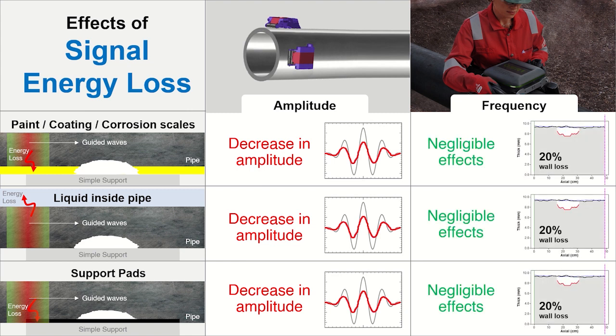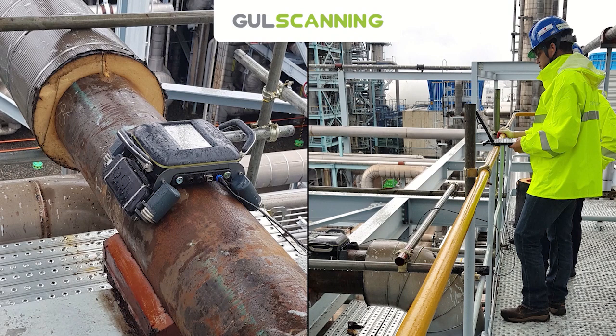GUL scanning's frequency-based method overcomes this limitation because coatings, liquid loads, and support pads have negligible effects on frequency-based results. By reducing the uncertainties of typical but conventionally challenging features such as shallow corrosion profiles or energy loss to paint, GUL scanning gives inspectors confidence in their inspection and delivers accurate data to asset owners.